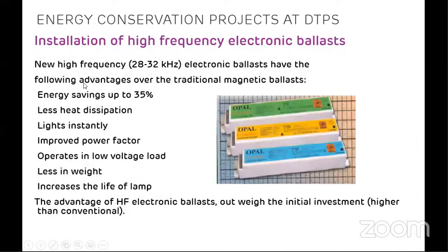So now if we replace this copper ballast with electronic ballast, we will get many advantages. What are those advantages? I'll tell you briefly. These electronic ballasts operate at higher frequencies, 28 to 32 kilohertz. They give energy savings up to 35%. As there is no magnetic core and copper coil, there is less heat dissipation. And the light lights up instantly. It gives full light output instantly. It improves the power factor.